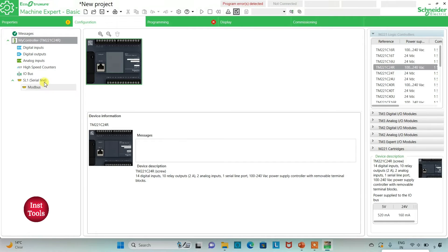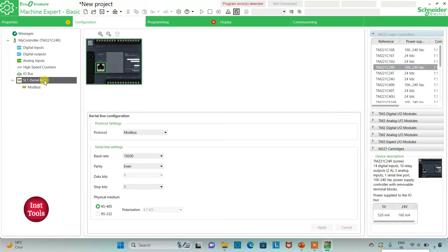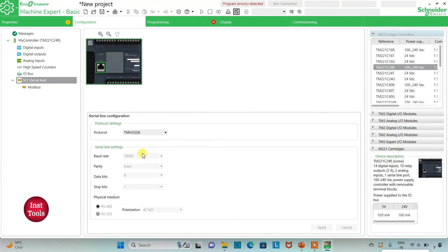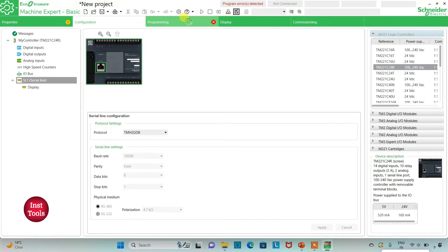After that, I can also go to Serial Line where I will select the protocol as TM2GDB. I can also set it as Modbus ASCII, TM2GDB, or Modbus Serial IO Scanner. I will keep it as TM2GDB for now and click on Apply. If the protocol is TM2GDB, there is no need to set the Serial Line settings. After that, I will click on the Programming tab.